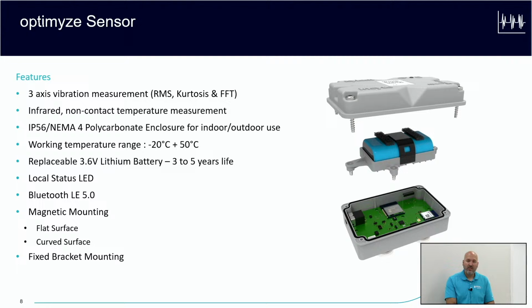Battery life is 3 to 5 years, so a bit of a wide range. The reasoning there is upon programming the sensor, you have the ability to tell it how often to take readings. So you can take readings every 5 seconds, all the way up to, say, once every day or 24 hours, right? So depending on where you fall on that scale and how often it's taking readings is going to kind of dictate whether you fall in the 3 or the 5 year range of the expected life there. And then if you're installing these near some sort of power outlet, we do have an optional power supply. There's a little port on the side of the sensor that you can plug in, and you would never have to worry about battery health there.